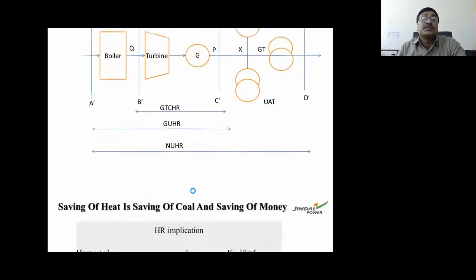I want to show you this because my previous colleague, Mr. Dinanath, has also shown some calculations regarding why the study of net heat rate and its calculation is very important, because it amounts to a very huge sum of money. For example, I have taken calculations for 1 kilocalorie of heat rate saving for a 600 megawatt unit. The generation for 1 day will be 14.4 million units. If GCV is 3000 kilocalorie per kg of coal, and coal cost is considered 2 rupees per kg, then it amounts to 9600 rupees per day. On an annual basis, it will be 35.04 lakh rupees, for only 1 kilocalorie.